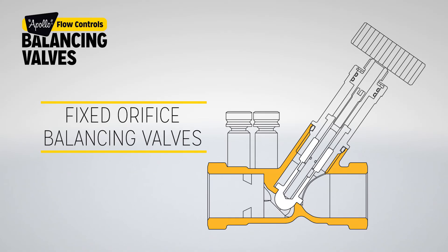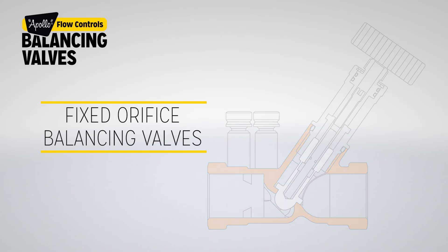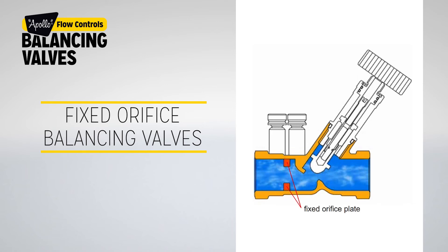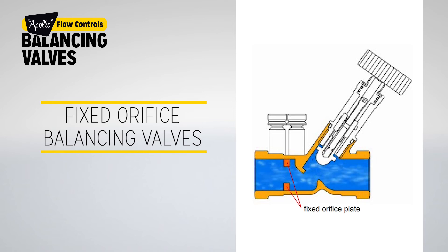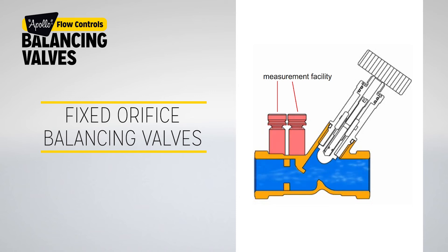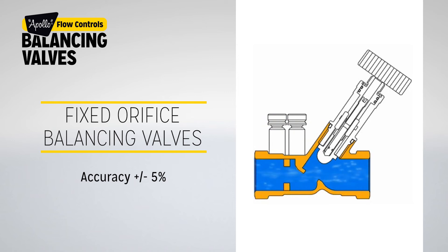Fixed orifice balancing valves: fixed orifice double regulating valves can be identified by a fixed orifice measuring device cast into the internal body of the valve. The CVS of these valves is fixed. The pressure differential is called a measurement signal, and the flow rate through this valve is calculated from that measurement signal. The accuracy of this type of valve is typically plus or minus 5 percent, dependent on the opening position.